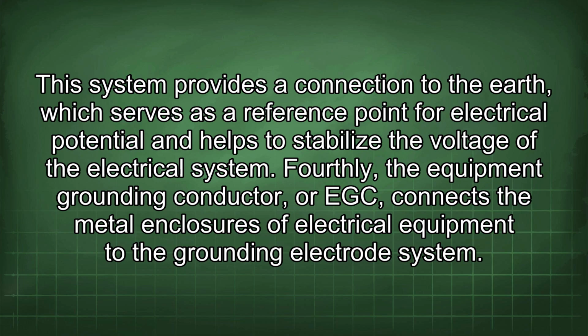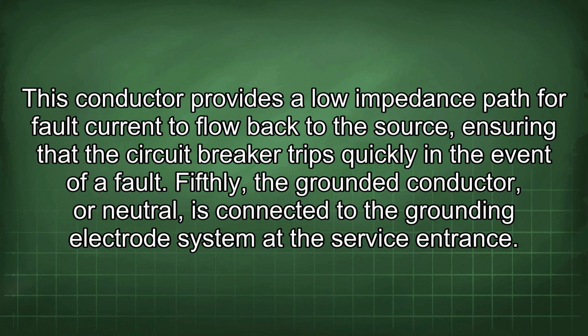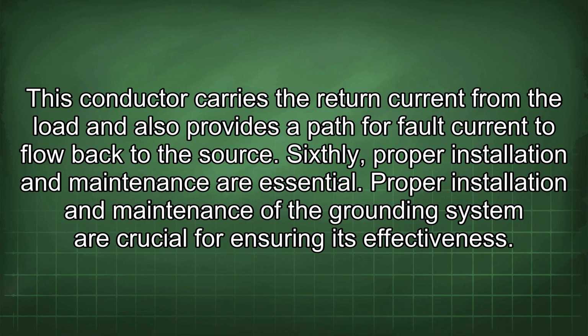Fourthly, the equipment grounding conductor, or EGC, connects the metal enclosures of electrical equipment to the grounding electrode system. This conductor provides a low impedance path for fault current to flow back to the source, ensuring that the circuit breaker trips quickly in the event of a fault. Fifthly, the grounded conductor, or neutral, is connected to the grounding electrode system at the service entrance. This conductor carries the return current from the load and also provides a path for fault current to flow back to the source. Sixthly, proper installation and maintenance are essential. Proper installation and maintenance of the grounding system are crucial for ensuring its effectiveness.